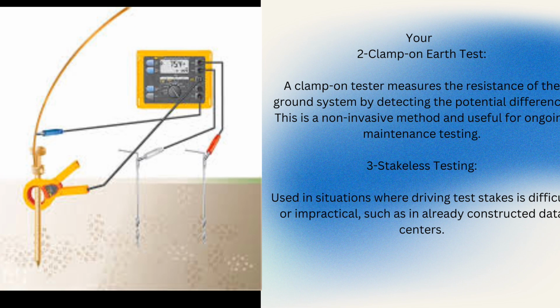Second, the clamp-on earth test. A clamp-on tester measures the resistance of the ground system by detecting the potential difference. This is a non-invasive method and useful for ongoing maintenance testing.